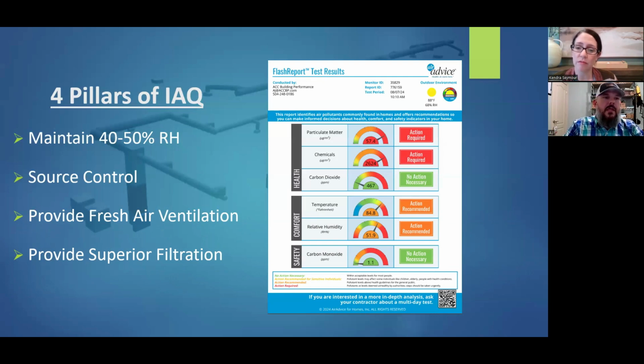To get into the weeds a little bit, when we do design work, we have to look up the extended performance data and the fan tables on the equipment. The manufacturer will give me a range of pressures that I have to stay within when I'm doing design work. The filters, the MERV 16s particularly, are extremely restrictive. Let's go through a hypothetical. If the manufacturer gives me 0.5 inches of water column to design to, and the filter eats up 0.2 of that, that leaves 0.3 for my coil, my ductwork, my grills, everything else. It's not practical. So you have to have a professional that's well versed in design work.